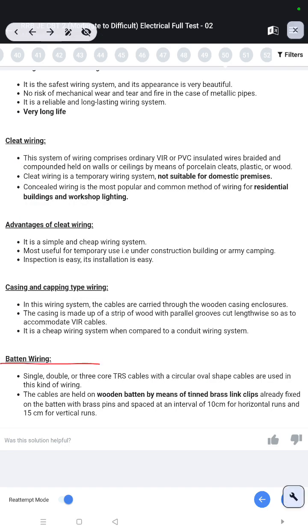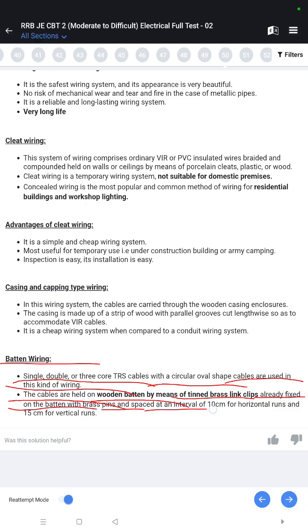Batten wiring. Single, double or three core TRS cable with a circular or oval shape is used in this kind of wiring. The cables are held on wooden batten by means of tinned brass link clips already fixed on the batten with brass pins and spaced at an interval of 10 cm for horizontal runs and 15 cm for vertical runs.